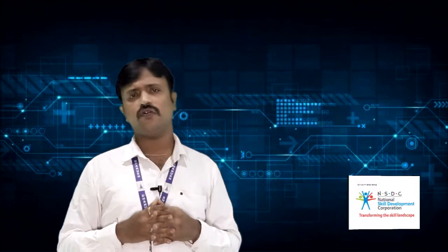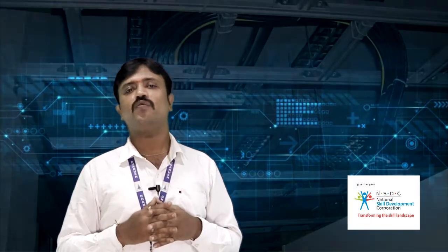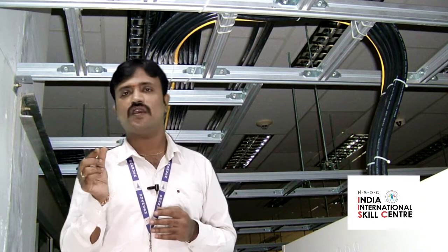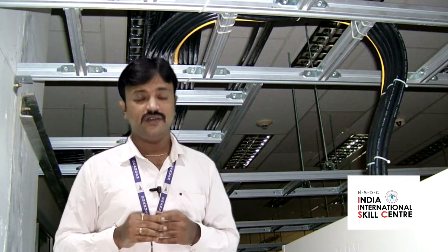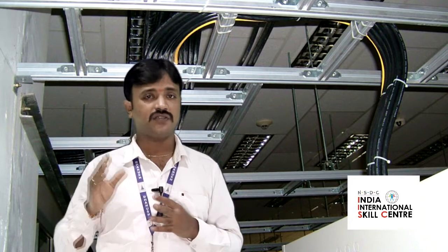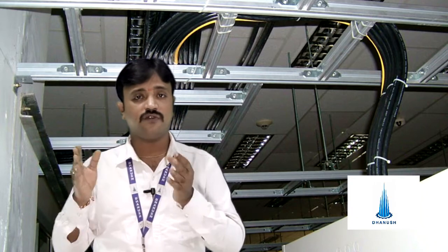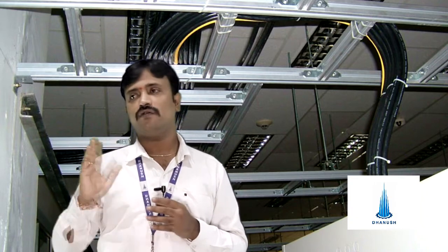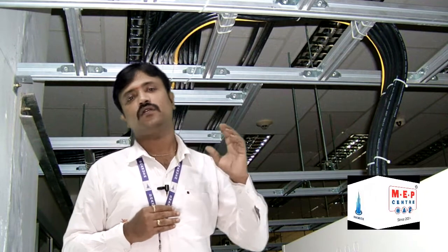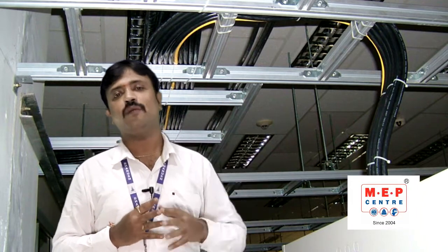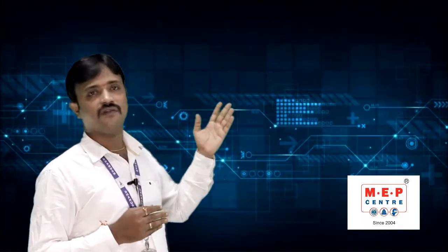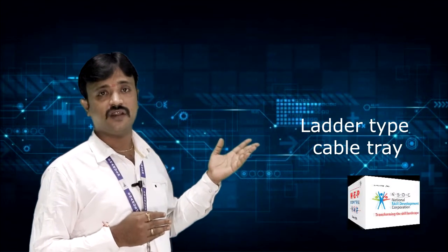The next one is we are going to study about the cable trays. Now, what is the purpose of cable trays? If you have a small bunch of cables, we go with the help of conduit pipes. But if you have bigger cables, we can't pass them through the conduit pipes. We have a large number of bigger cables, so we can't go with conduit pipes. So we go with an equipment called cable trays. As you can see, we have different types of cable trays: perforated, ladder type, and mesh type.